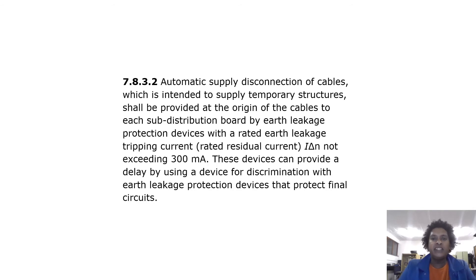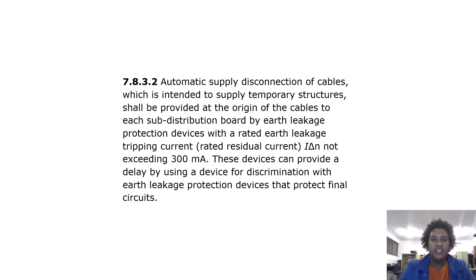Automatic supply disconnection: cables intended to supply temporary structures shall be provided at the origin of the cables to each sub-distribution board with earth leakage protection devices rated not exceeding 300 milliamps. These devices can provide a delay by using a device for discrimination with earth leakage protection devices that protect final circuits.